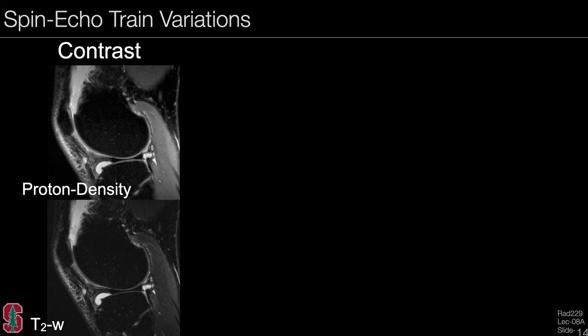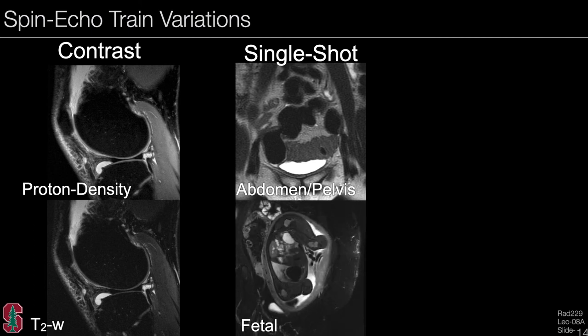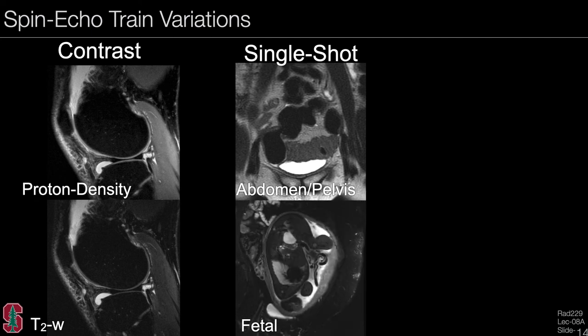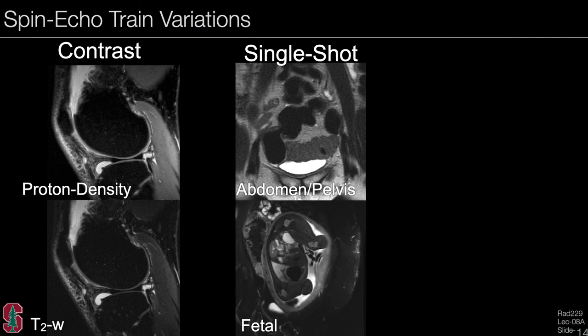Simply by the order in which k-space is filled, we can achieve proton density weighted imaging — where muscle and cartilage appear bright compared to fluid pockets in the knee — or T2 weighted imaging where muscle and cartilage are relatively dark. An extreme case is single shot imaging, where an entire image is acquired in one echo train, very useful for imaging the abdomen and pelvis to freeze random motion. Reasonable quality images can be achieved in approximately a quarter to a third of a second or less.